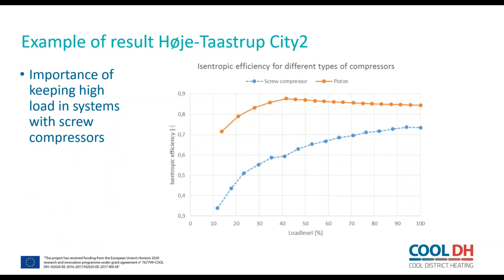This is also the one I mentioned in the results, the main learnings, that for the screw compressor, you need to have a high load level to get them working properly. When you go below 50%, you see that the efficiency is quite heavily reduced, whereas the piston compressor works quite good at most of the loads.